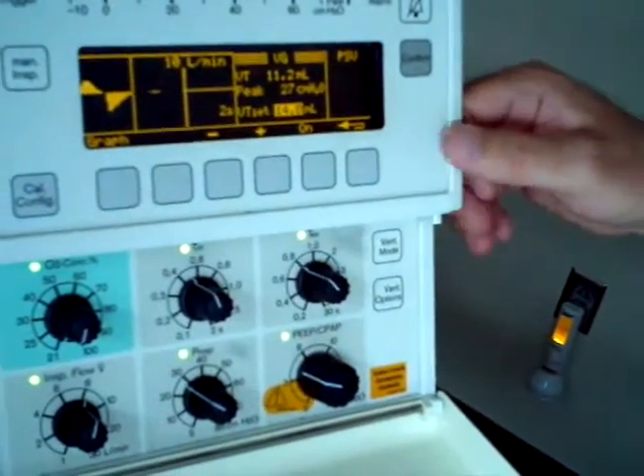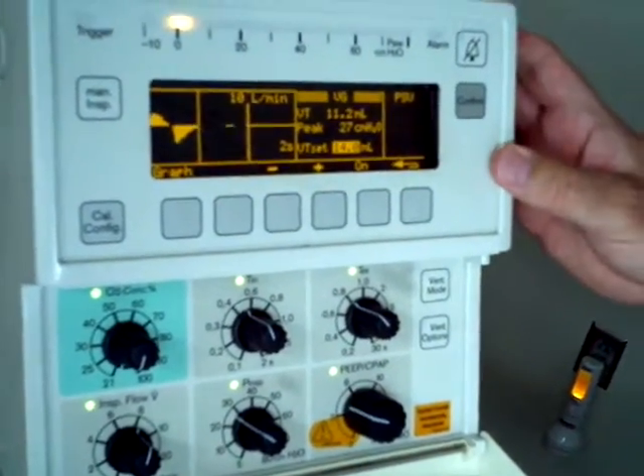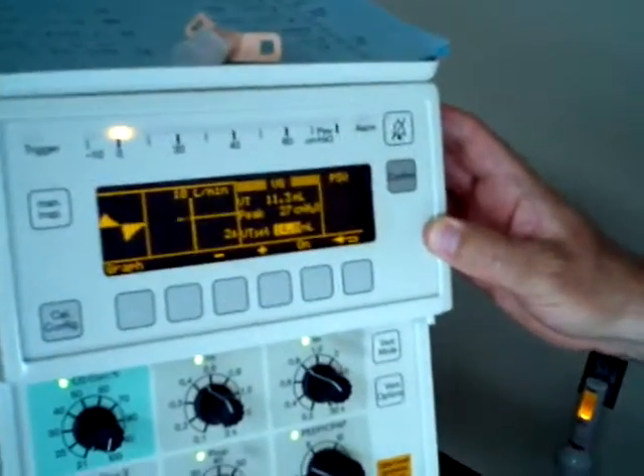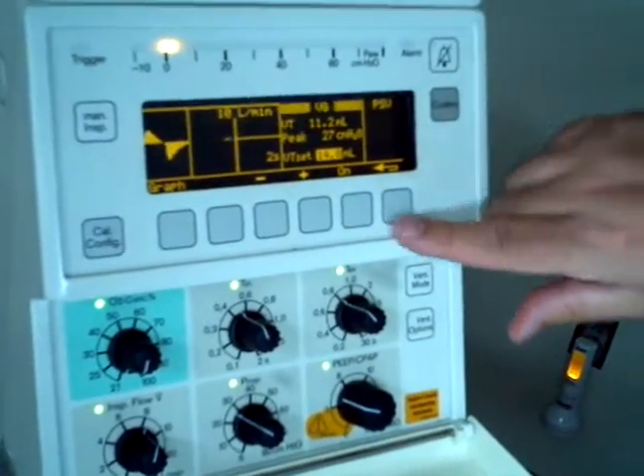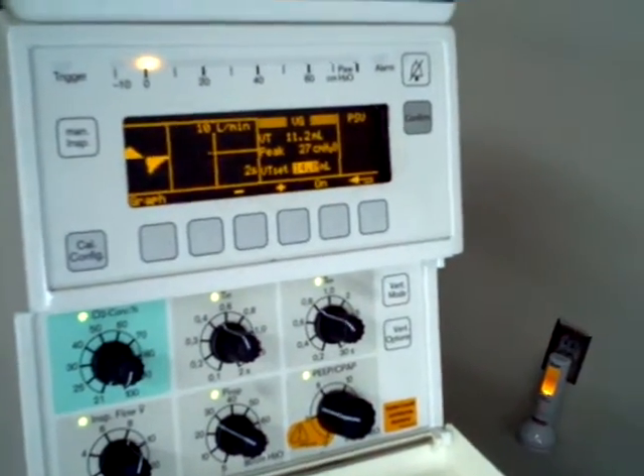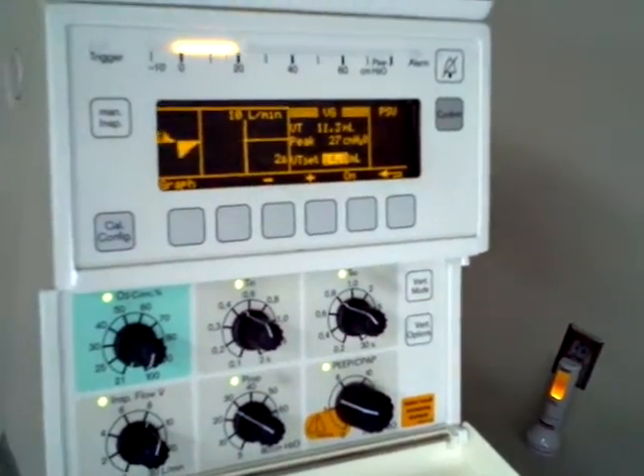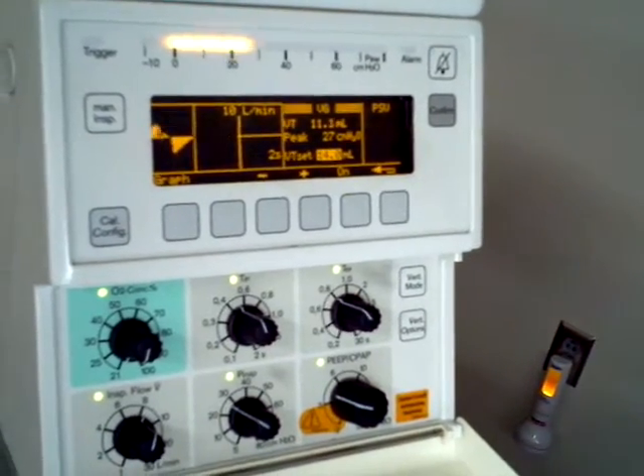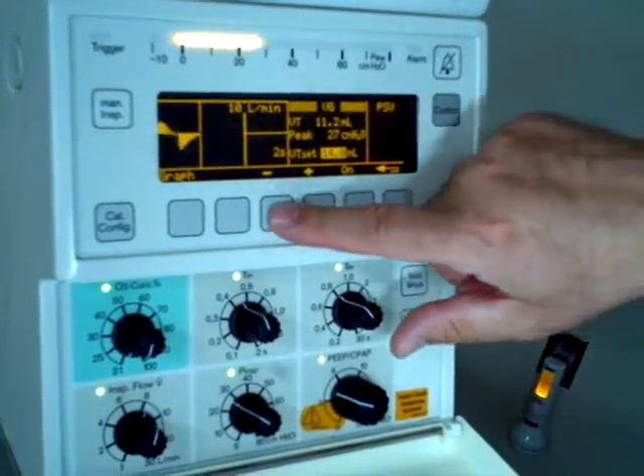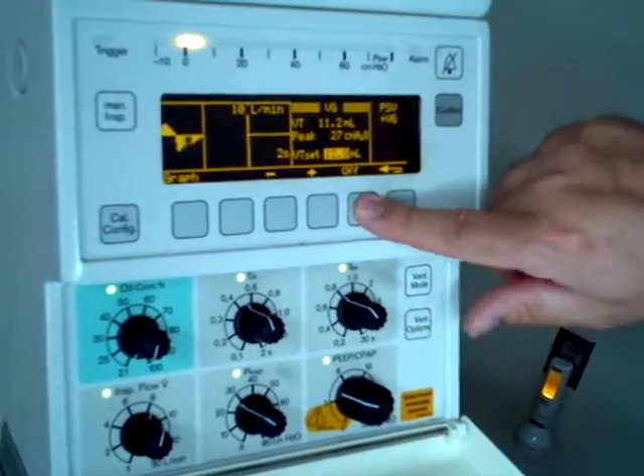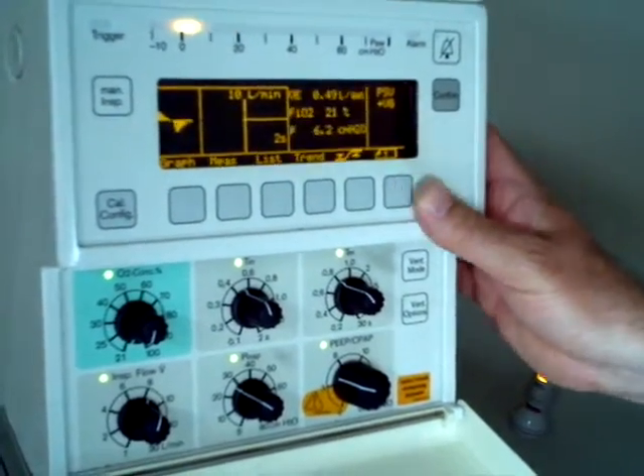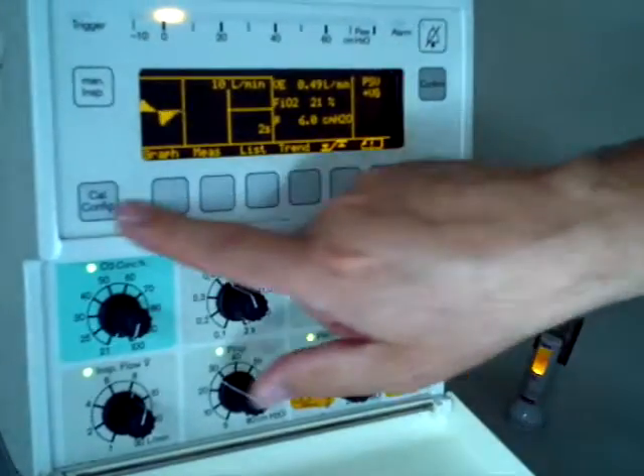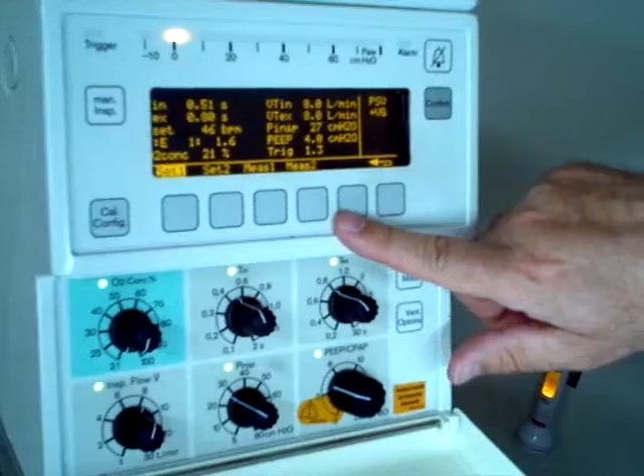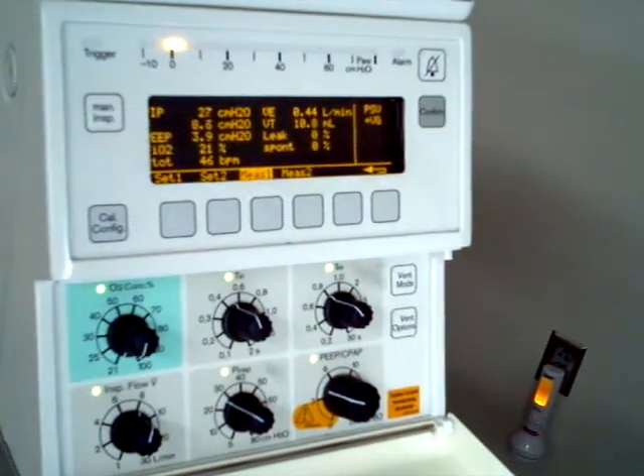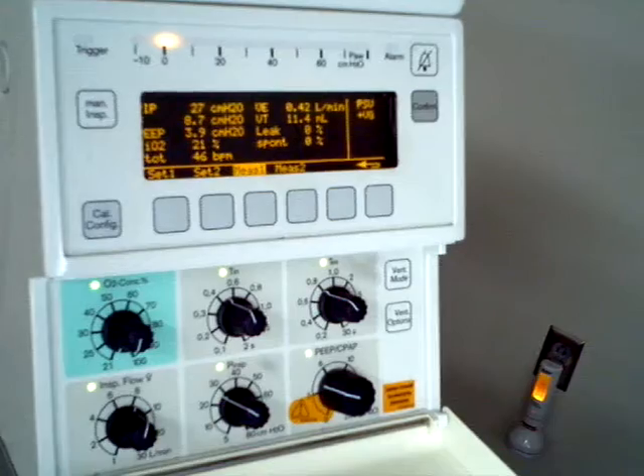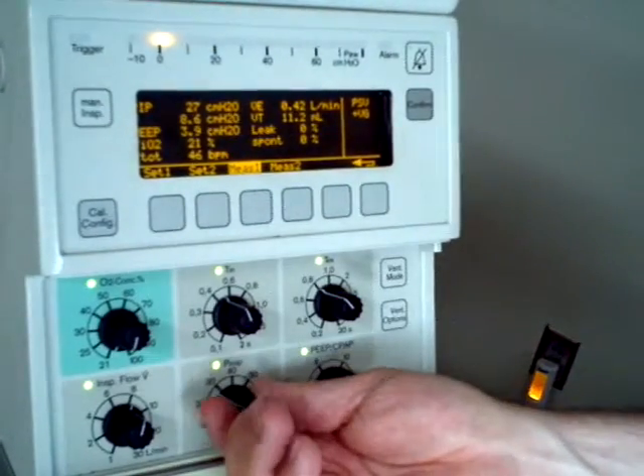Options, volume guarantee. Let's say we want to make the tidal volume 12. What's it say on there? 11. So we're going to make it 12. It's on 11. We'll make our volume guarantee 12. Activate the volume guarantee. Okay. Check our tidal volume. And it's 10.8. Again, I need to go up on my peak inspiratory pressure.